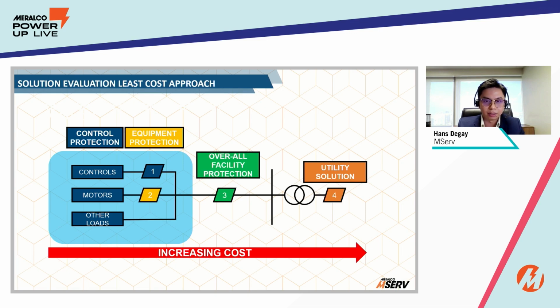There are many products available to minimize power quality issues. However, since it entails capital costs, here is a quick overview on the cost implication. If the source of the problem could be identified or there are specific equipment that are sensitive to power fluctuations, then the solution can be minimized if installed near the equipment. As we go more upstream, syempre mas mahal. The cost will increase. For example, if you want the entire facility to be protected from voltage sags, naturally, the cost will be significantly higher than just protecting a single load. Often, other loads such as lightings can be neglected.